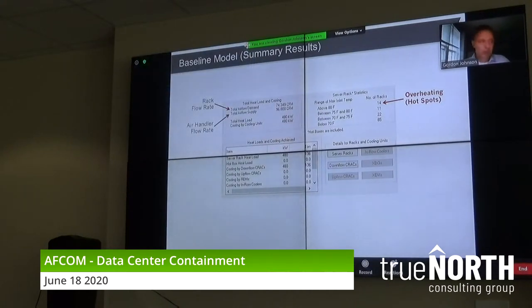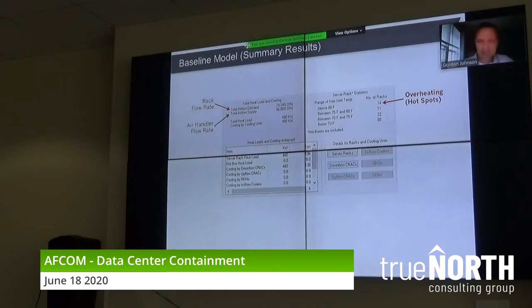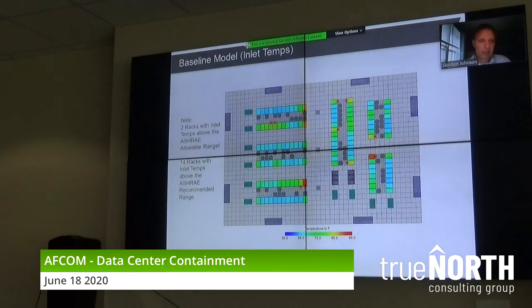I've got 14 racks above 80.6 degrees in this data center. And that shouldn't be the case because the supply air is 62 degrees. I should not have overheating, but without containment, again, I'm wasting air. I have more air than I need, and hot air is coming around the top of the racks and around the edge of the cabinets.